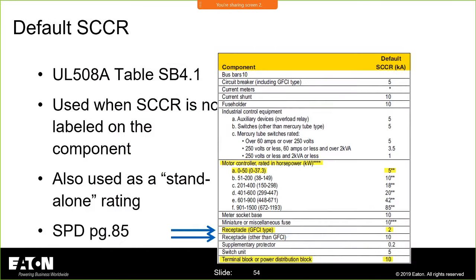UL 508A has a table, which I have a love-hate relationship with, because it talks about the default short circuit current rating, and what do we learn? We just learned that circuit breakers do not have a short circuit current rating, right? Fuses do not have a short circuit current rating. So we've got some work to do on this table, but in any case, you'll see there are default SCCR ratings for things like receptacles, supplementary protectors, and switch units. That's a default: if it's not labeled, that's what you go with.